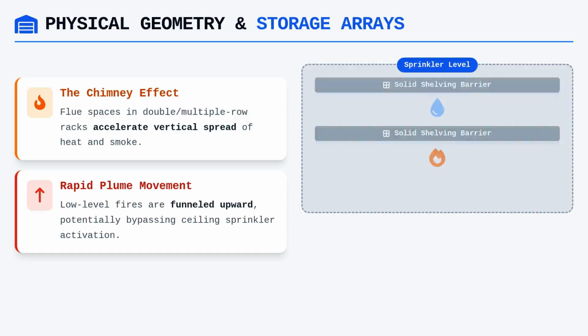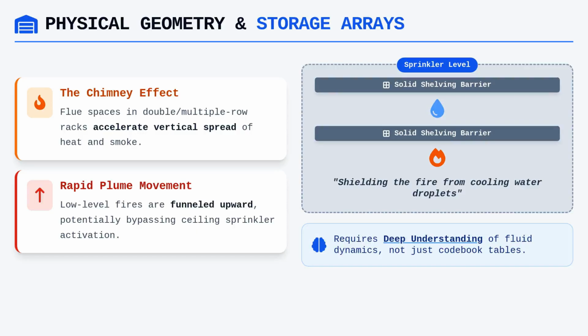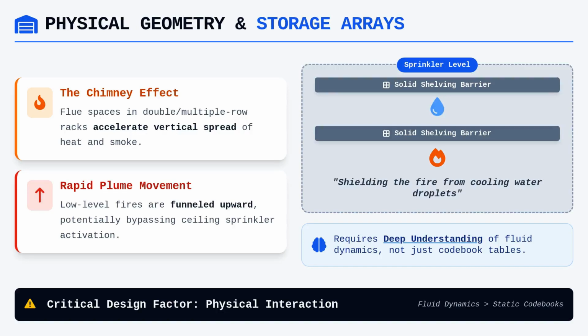We must also consider how solid shelving interferes with the cooling effect of water droplets, effectively shielding the fire from the sprinklers. Designing for these environments requires more than just following a table in a code book. It requires a deep understanding of how fire plumes interact with physical barriers within the rack structure.